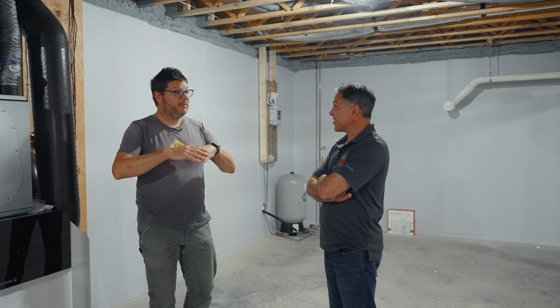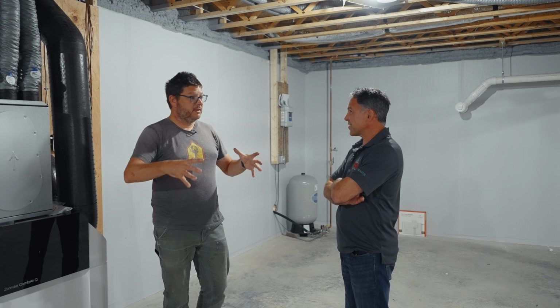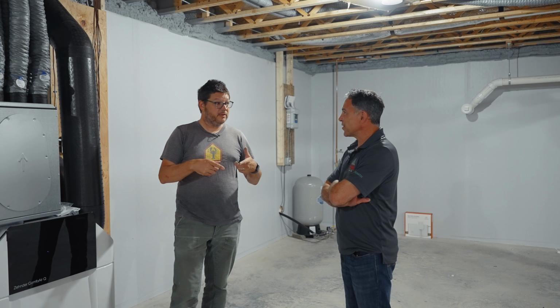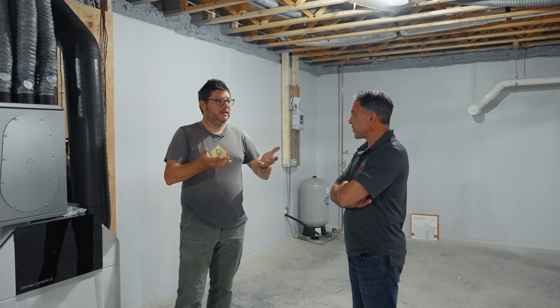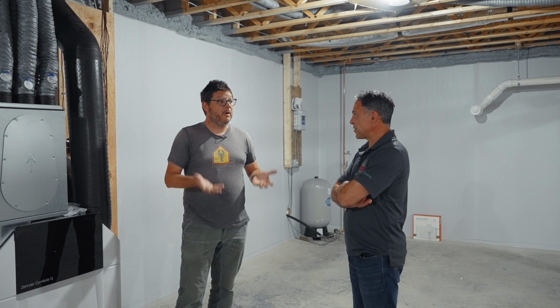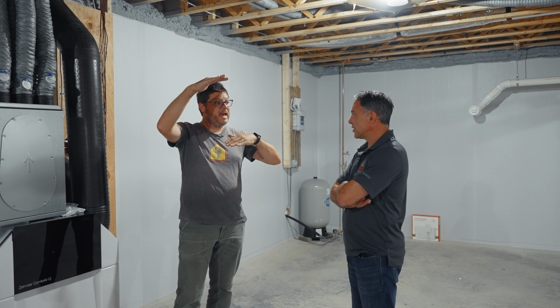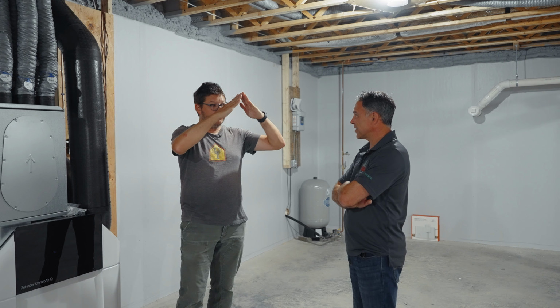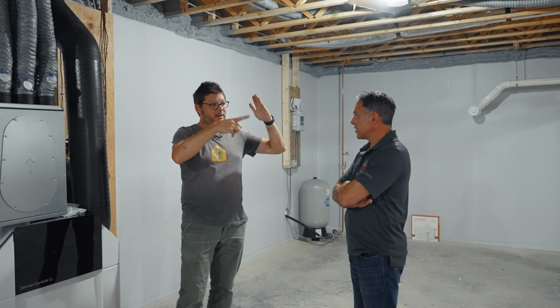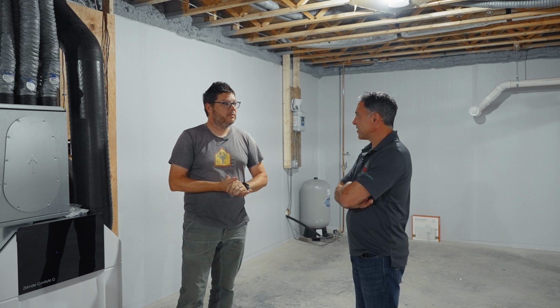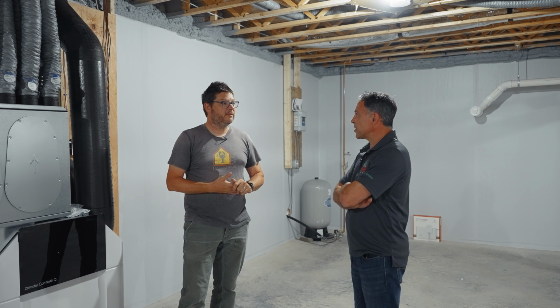A lot of people won't take the conditioned air in the basement and run it through their systems, and the humidity levels, especially in summertime, can go up. Same if you put your air handler in the attic and spray foam your roof, but don't run the attic air through the air handler—you end up with serious moisture problems in your roof, because you need to run it all.